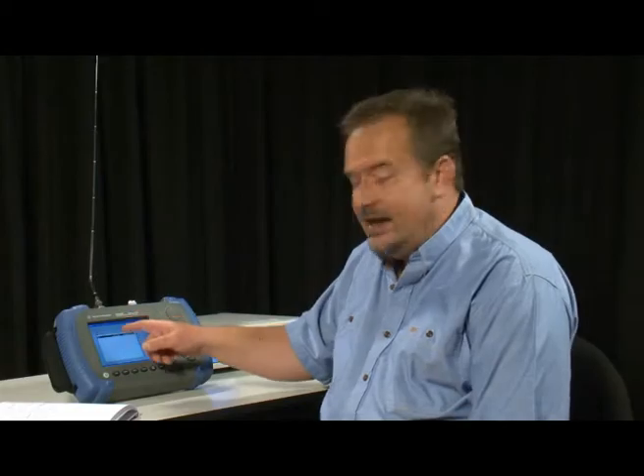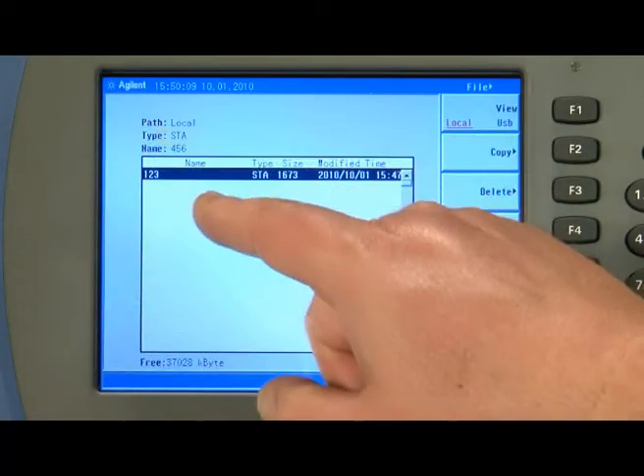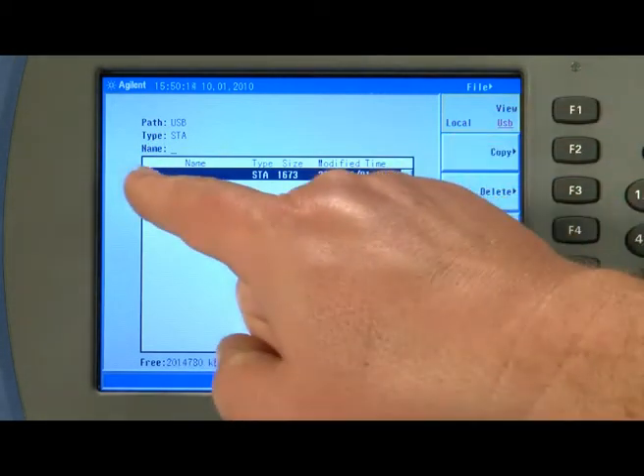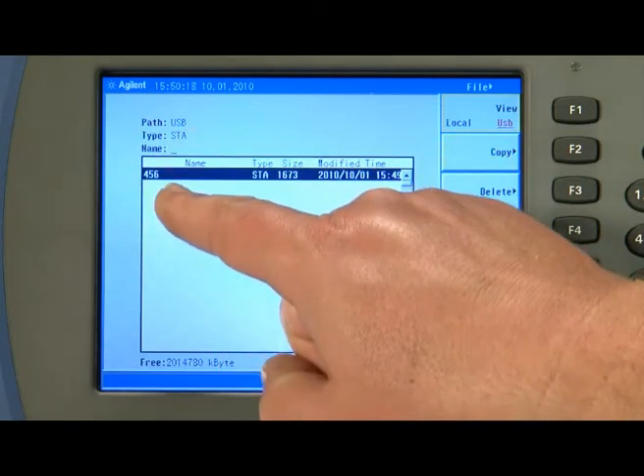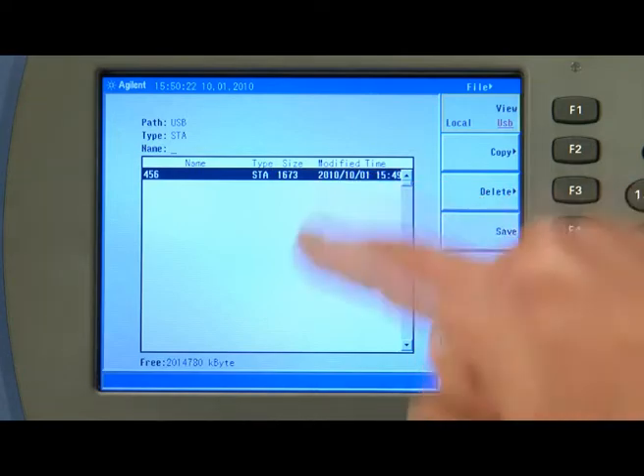Now the reason you cannot see that file saved on this display here is because the path for the display is still set to local. So let's view the USB stick and here you can see on the USB stick it says the path is USB and we have a file called 456. It is a state saved again on the 1st of October 2010.